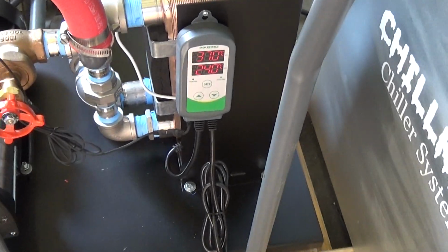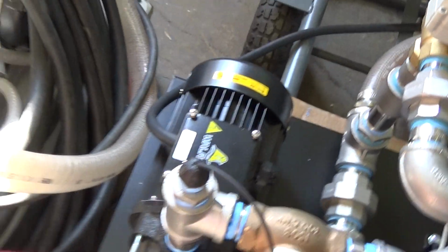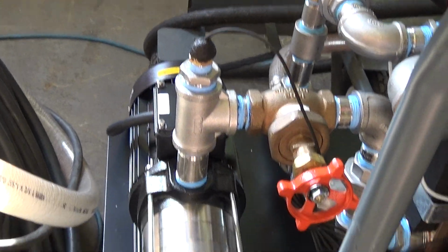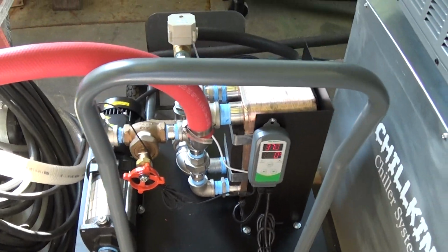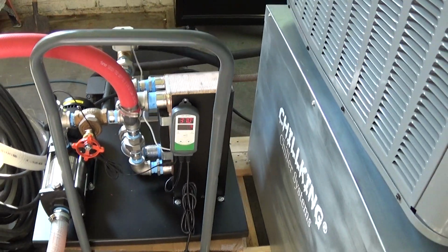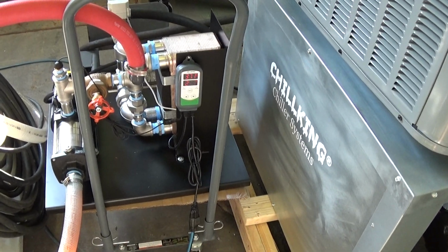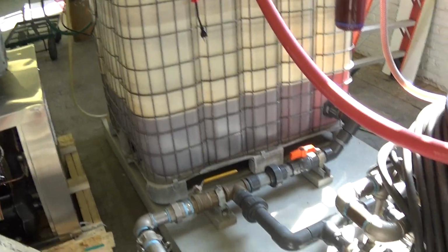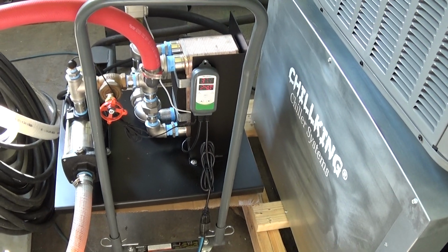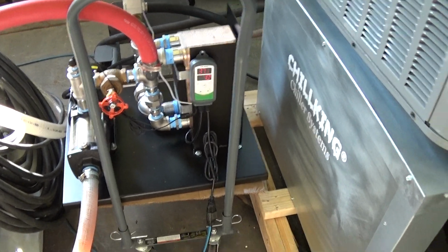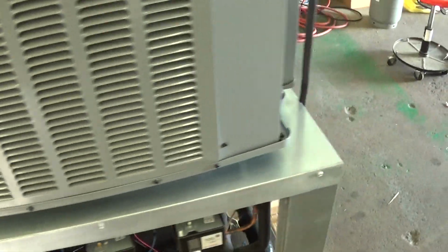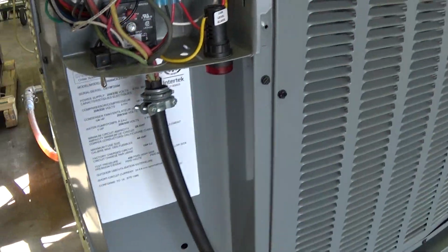So what does that mean? That means that the probe from this Inkbird controller comes right into this well right here, and that's measuring the temperature of what's being drawn from the process. So the reason we have all this, again, is because one, we're going to have an outdoor chiller, so we have this isolation exchanger to isolate the oil or the process from what's going on outdoors, and also for tighter tolerance and temperature control. Because in the world of chillers, we can't have a super tight differential, otherwise we'll be short cycling the chiller.